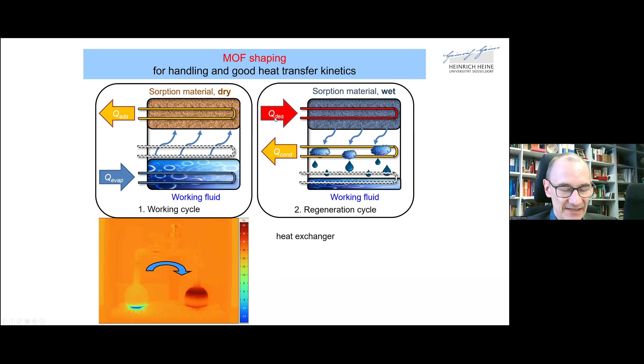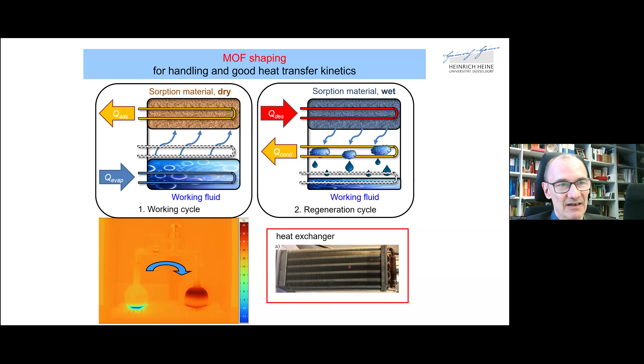For this technology, you have to have adsorption material in close contact with a metal surface from which the heat of adsorption or desorption is dissipated or brought in. That means we need a real heat exchanger, perhaps filled with a MOF, or the MOF brought in between the lamellas of this heat exchanger, so that we have a device which dissipates the heat of adsorption and brings back the heat of desorption as quickly as possible, at best through only a thin layer of porous material.